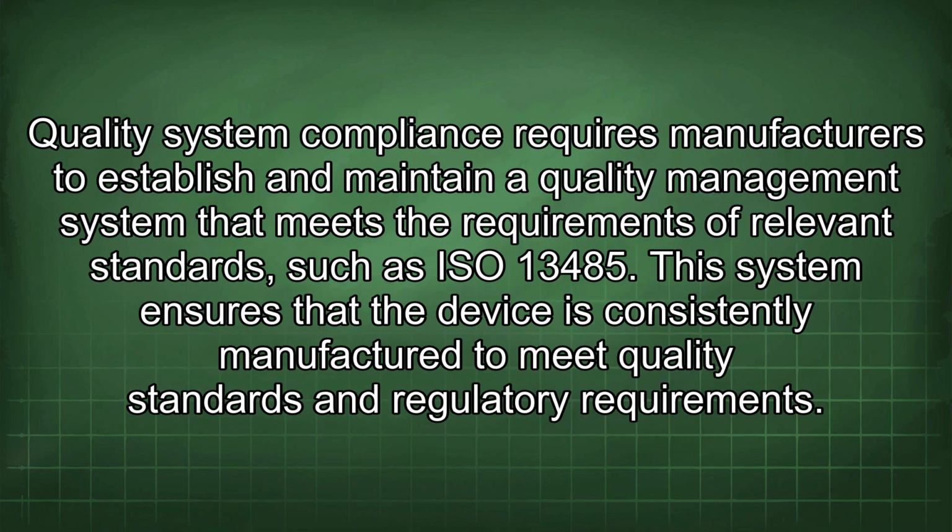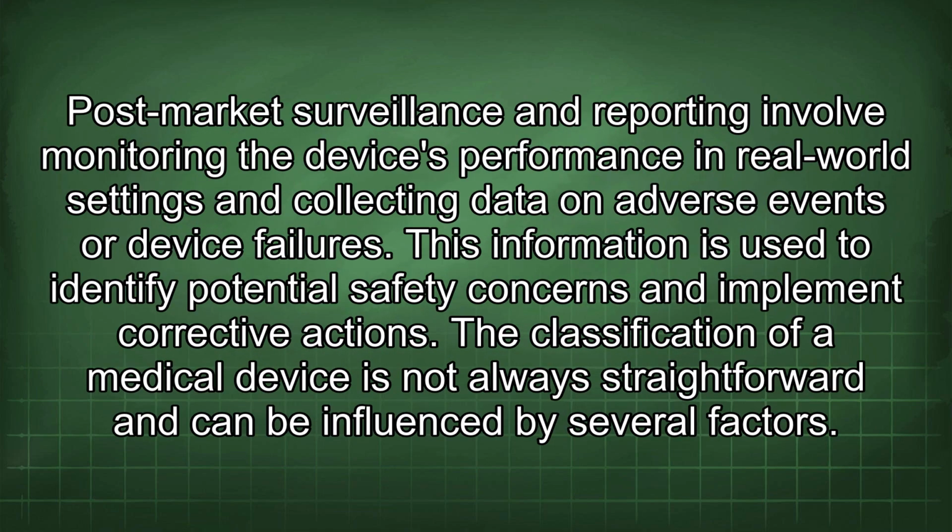Quality system compliance requires manufacturers to establish and maintain a quality management system that meets the requirements of relevant standards, such as ISO 13485. This system ensures that the device is consistently manufactured to meet quality standards and regulatory requirements. Post-market surveillance and reporting involve monitoring the device's performance in real-world settings and collecting data on adverse events or device failures. This information is used to identify potential safety concerns and implement corrective actions.